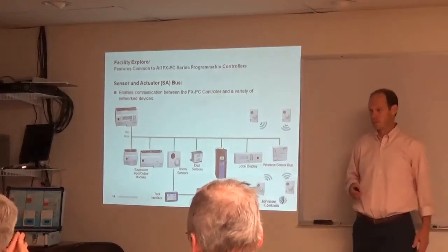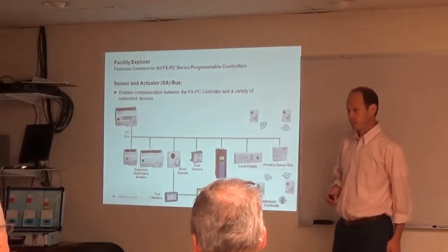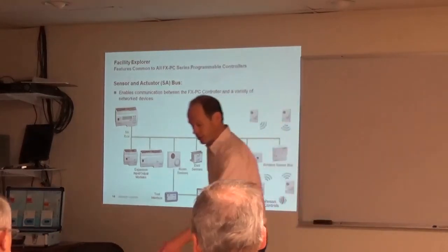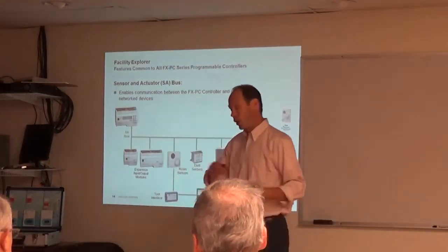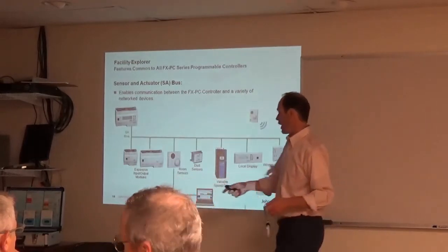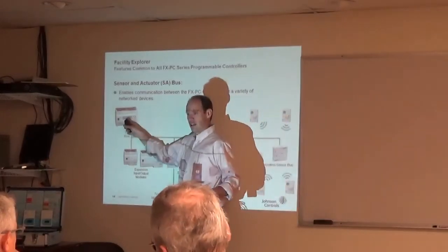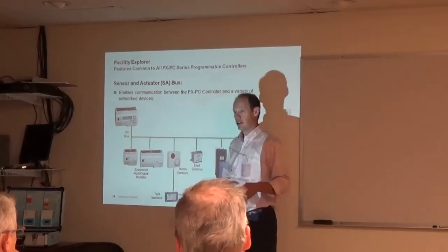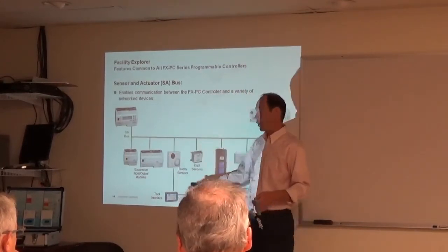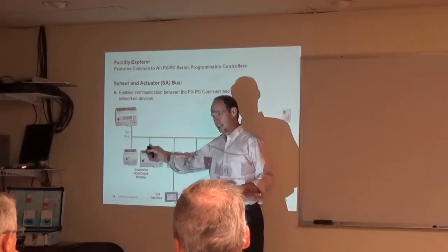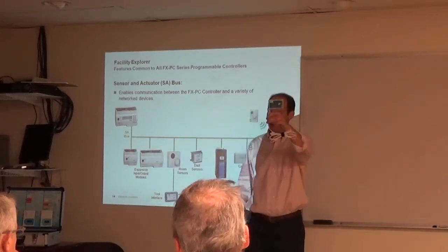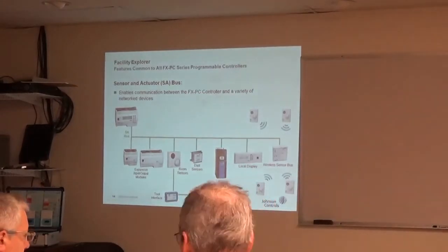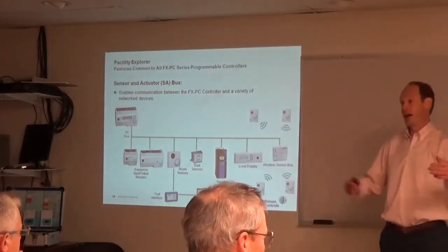Do you have a VAV controller with the wireless built in, or do you have to add the wireless? Yeah, each one of the controllers are the same for wired or wireless. So if I have a PCG controller, a PCA controller, a PCB or a PCX controller, they're all standard. If I want to make it wireless, I put the 128 switch on and plug in a flag. And that makes it a wireless device. So there's nothing built in, you just add the flag after.